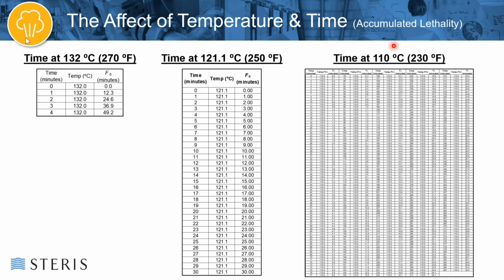So steam sterilization can actually be operated down to temperatures around 110, maybe 105 if you've got a good steam sterilizer. But just like over here, when you increase temperature and you reduce time, if you decrease the temperature, you have to increase time. So for those of you that don't have an eagle eye, this is actually 387 minutes of exposure down here, which is roughly 6.5 hours long.